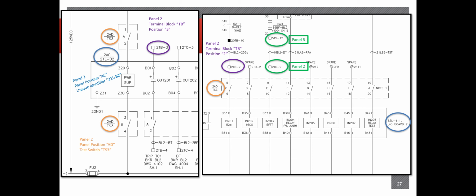It's a specific identifier for a cable that may be leaving or coming back in. As I said before, that 52-1 is a breaker contact. That is going to be identifying whether the breaker is open or closed, which is extremely important for the relay to see, to know when to operate and when to not. You don't want it to keep opening a breaker that's already open. That's just silly and doesn't make any sense. And you definitely don't want it closing in when it's already closed in.